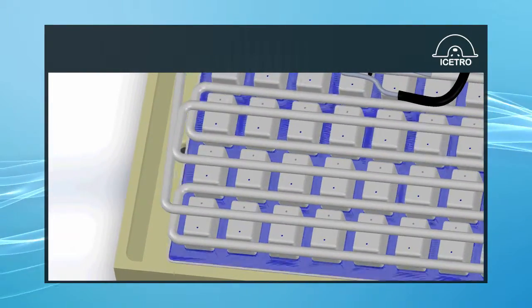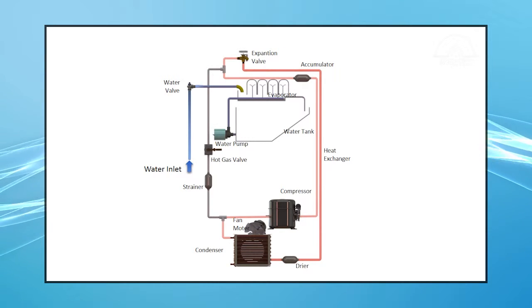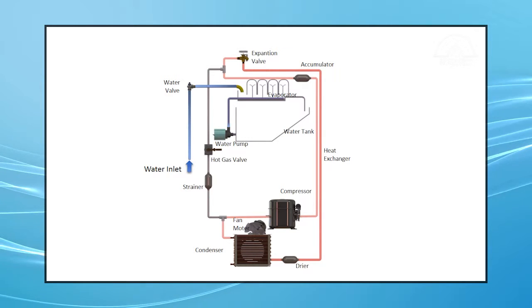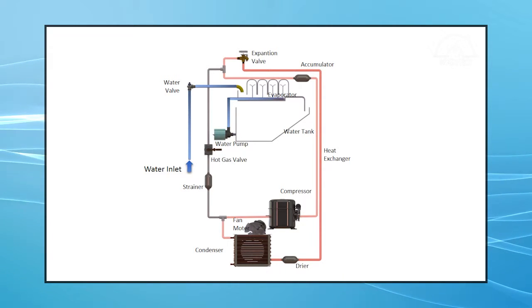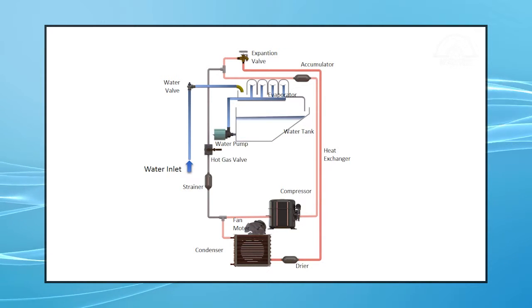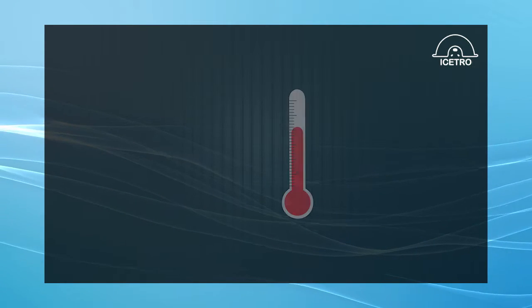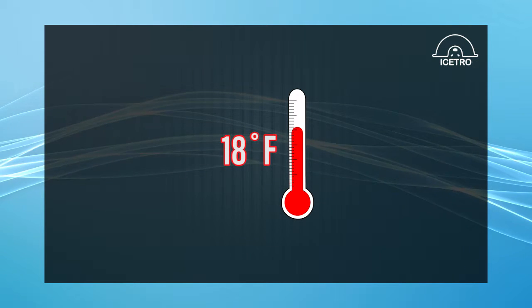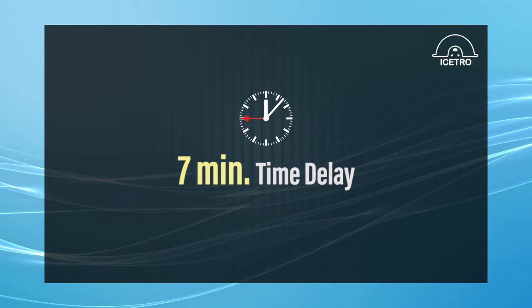At the beginning of the freeze cycle, the water valve shuts off and the water pump compressor and condenser fan motors start. The spray tube and nozzles are now filling cube cells in the freeze cycle and ice begins to form. This process continues until the evaporator reaches 18 degrees Fahrenheit. The controller board then initiates a seven-minute time delay to complete the freeze cycle.